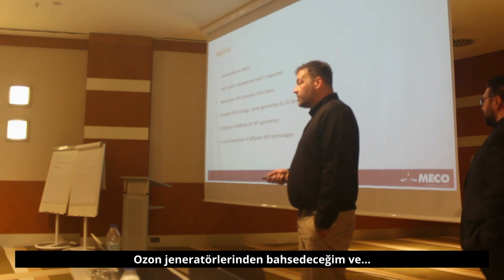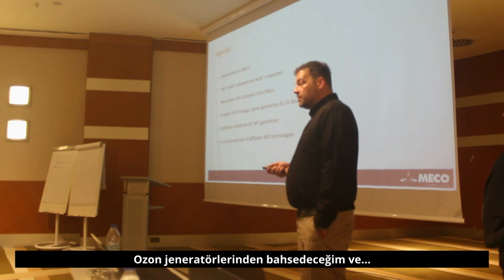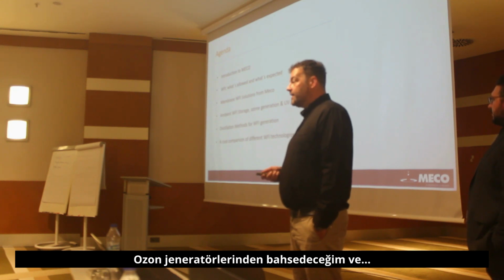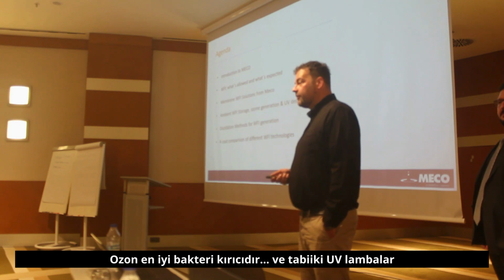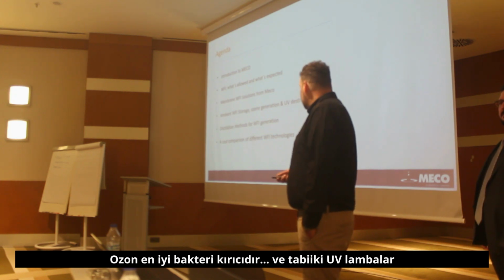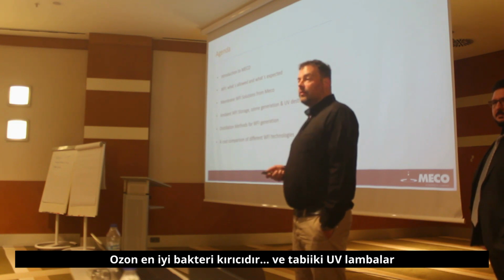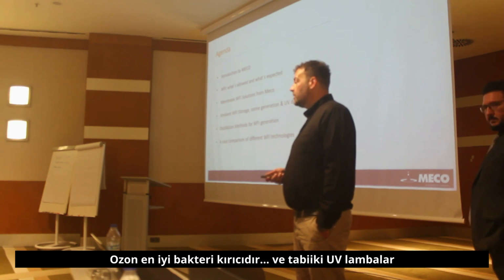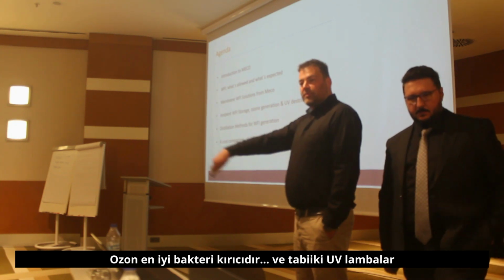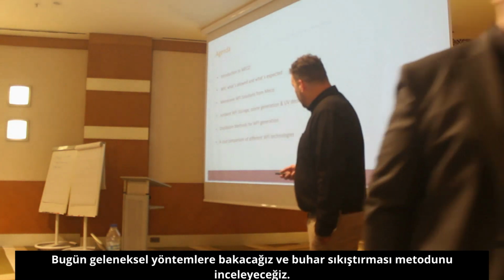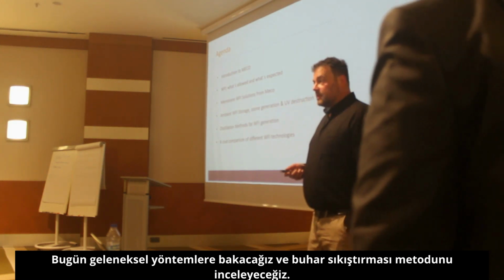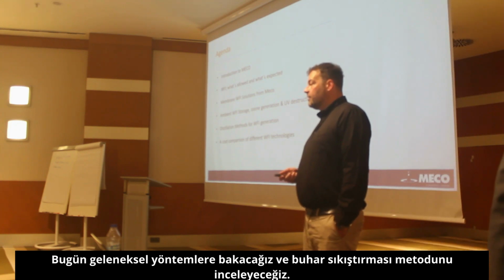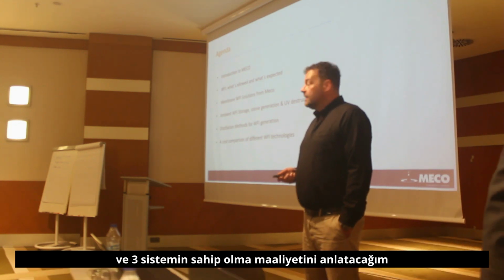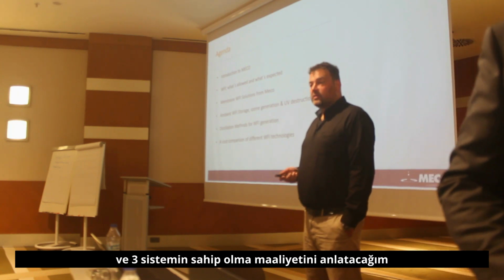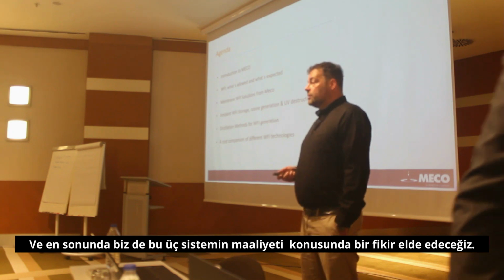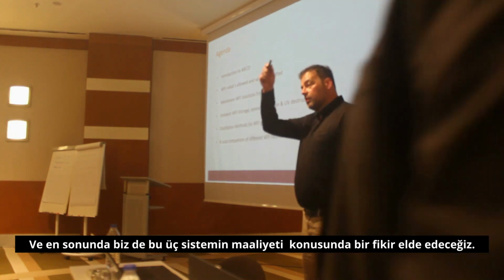I will also cover ozone generation, because ozone is an agent that we use best to protect our water for injection from bacterial growth at ambient temperatures, and ultraviolet is going to destroy our ozone, because we must make sure we don't send ozonized water into the loop to your user points. We are going to then look at the conventional methods that most of us know, distillation from multi-effect and vapor compression, and the pros and cons of each of those systems. And in the end, we're going to do a total cost of ownership comparison of all 3 systems.